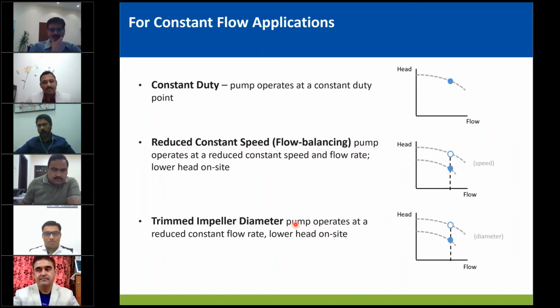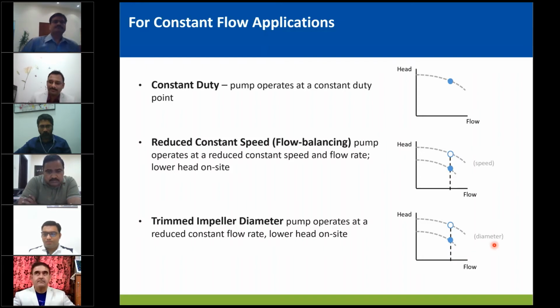Now the easiest but old practice is to trim the impeller, which is also somewhat similar to reducing the speed, but you can't increase the head again if you require it in the future. So once it is trimmed, you lose that opportunity of future-proofing that pump for future requirements.